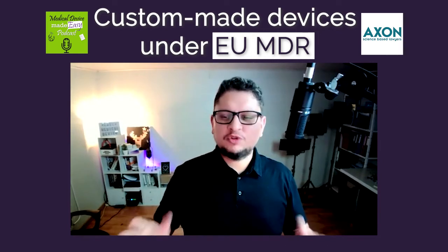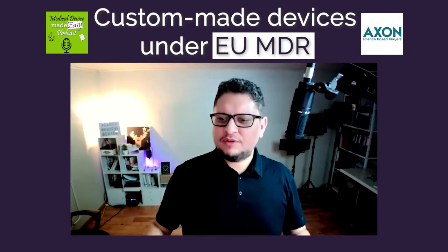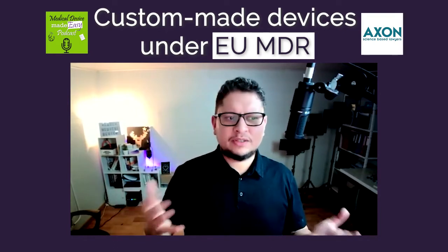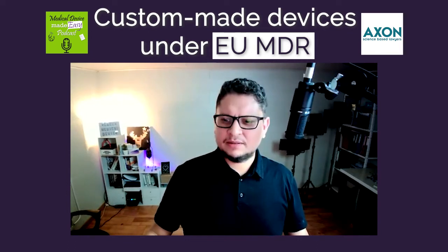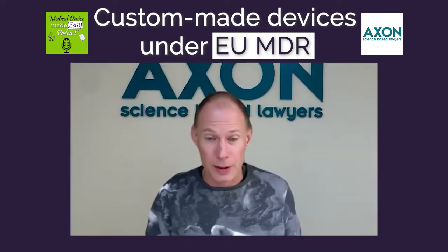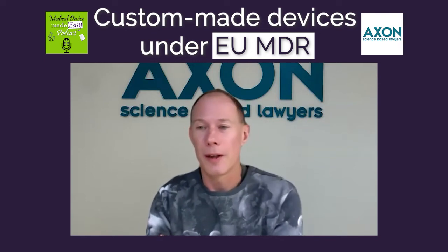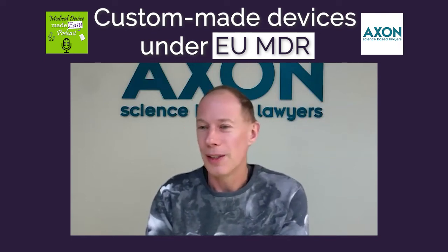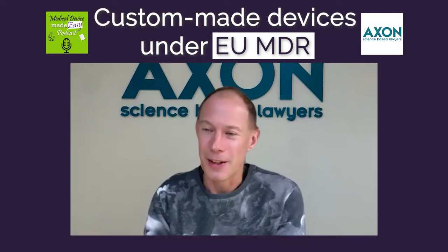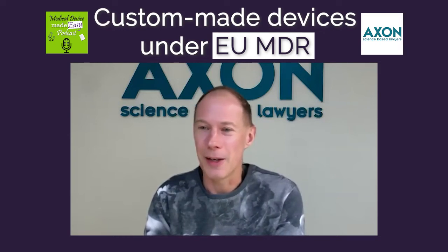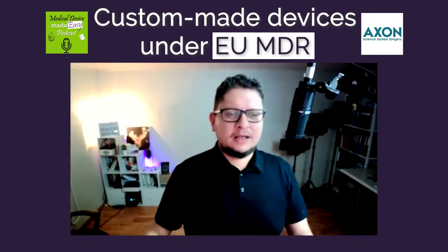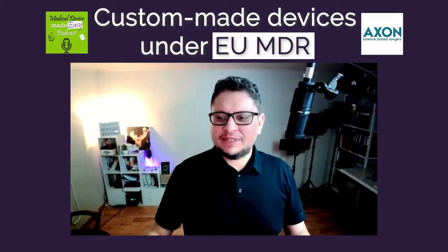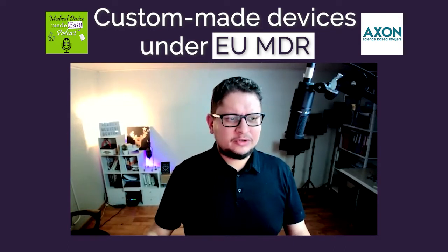So they are really coming to verify the quality management system and then providing you, is it a CE certificate or is it an ISO quality management system certificate for custom-made devices? Well, that's a good question. I mean, if it would be an ISO certificate, you would need a standard that is certified again, and that's not specified in the MDR. So it's basically an EC certificate. So EC for custom-made device. I mean, for specifically the scope of your device, but looking only at a quality management system. So it's something that is interesting here.